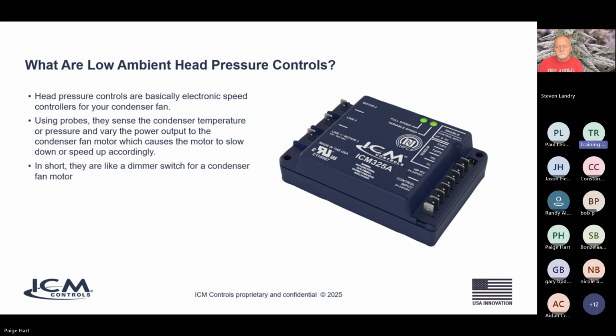But I like to compare this to a dimmer switch. In short, these are very much like a dimmer switch in your house. You have a dimmer switch on the wall, you adjust the resistance of that little dimmer switch potentiometer, and that changes the output voltage to the light bulb. Well, in a very similar way, when you use the temperature probe, it changes resistance according to the temperature of the condenser coil, and that changes the output voltage to the fan motor. So it's a dynamic, automatically controlled, so to speak, dimmer switch.